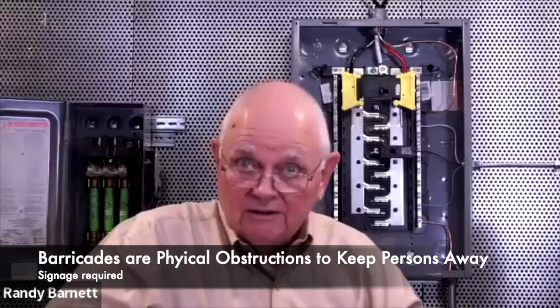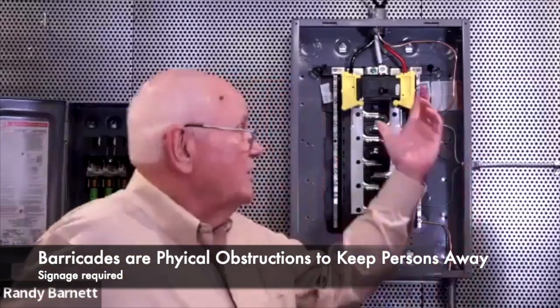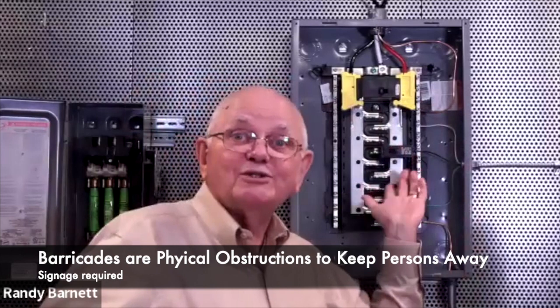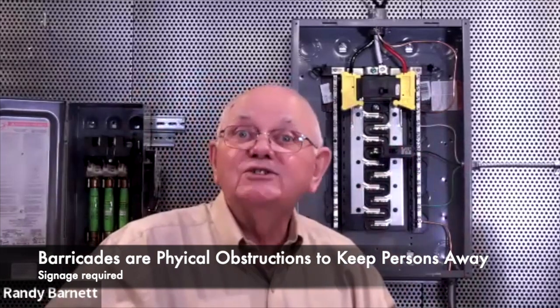But once again, there's no physical barrier tape, barricade, right? Physical tape to establish this barrier, that's called a barricade. Now, where are we going to set the barricade? Where are we going to put this piece of red tape or the chain, whatever it is? The barricade is also a physical obstruction, just like a barrier is. However, the purpose of the barricade is it keeps people out. So I'm not going to rely on a little piece of rubber to keep some unqualified person from reaching in here and touching something they shouldn't, huh?